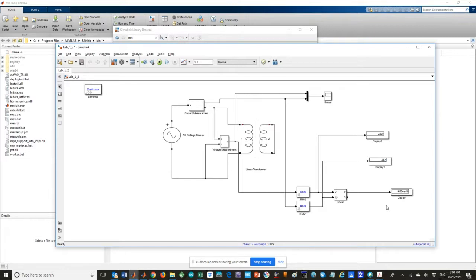If we need to do a short circuit, either for a transformer or for rotating machines, we have to take care. A physical short circuit is a wire between two terminals for the transformer, and for the machine it's done by holding the rotor, blocking it by hand or using a system to block the rotor from rotating. This is the short circuit test for the machine.